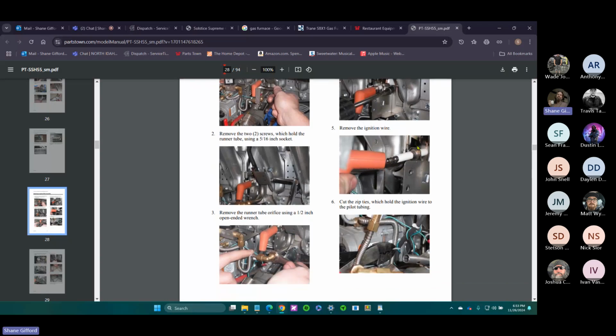But then your thermocouple is also attached to this pilot assembly. And I hate to say it, but these Pitcos, they're a pain in the nuts, dude. Get ready to get your knuckles cut up, because that's just what's going to happen with these real knuckle busters. But your thermocouple is in there, and that's going to usually have either a wire with a spade connected to it, or it's going to be that copper that we saw earlier. So you'll want to just pull this whole thing out to even see your thermocouple just to clean it.